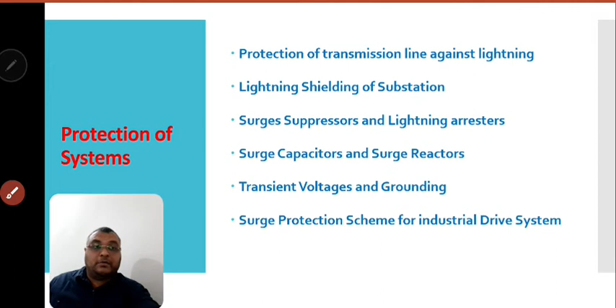Okay, so after protection of the system, we will go through insulation coordination. Insulation is a very important factor when dealing with any equipment or power system protection devices, because whenever a transient occurs, the first effect is on the insulation. It's the first part that comes into the way of the transient, and it's the first to get damaged.